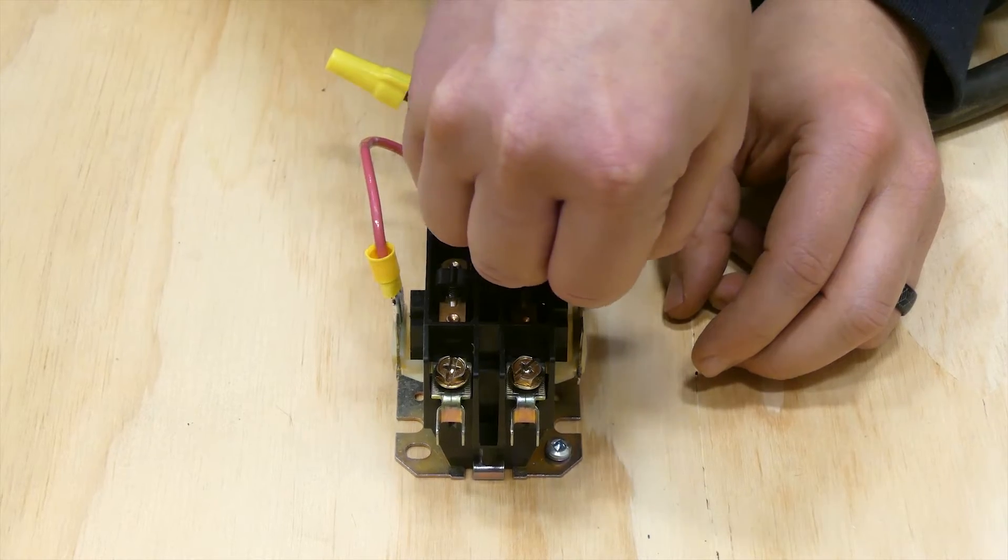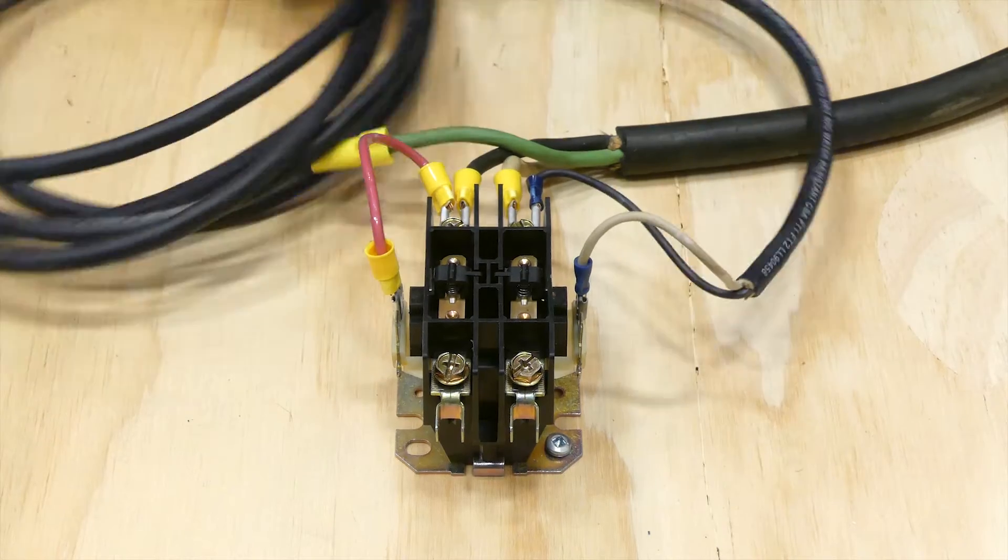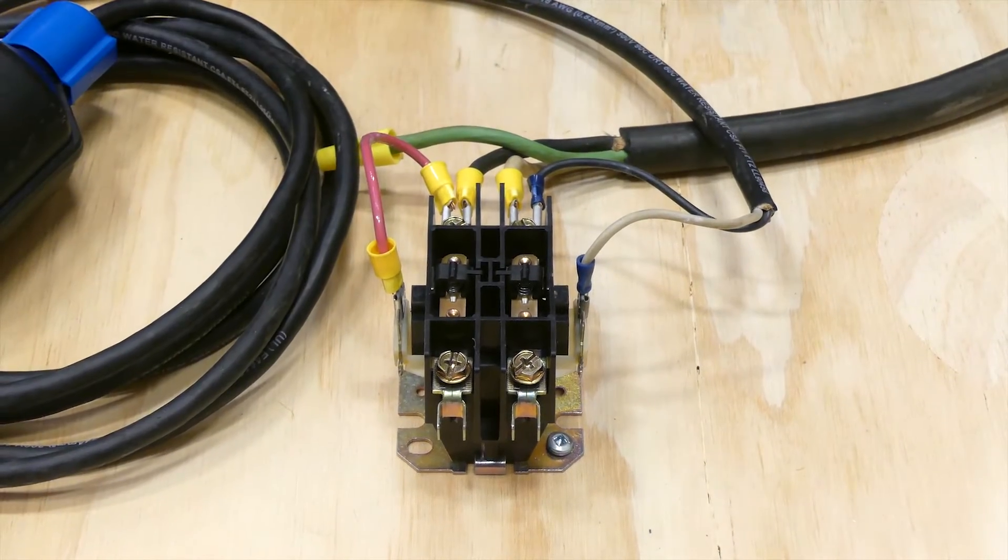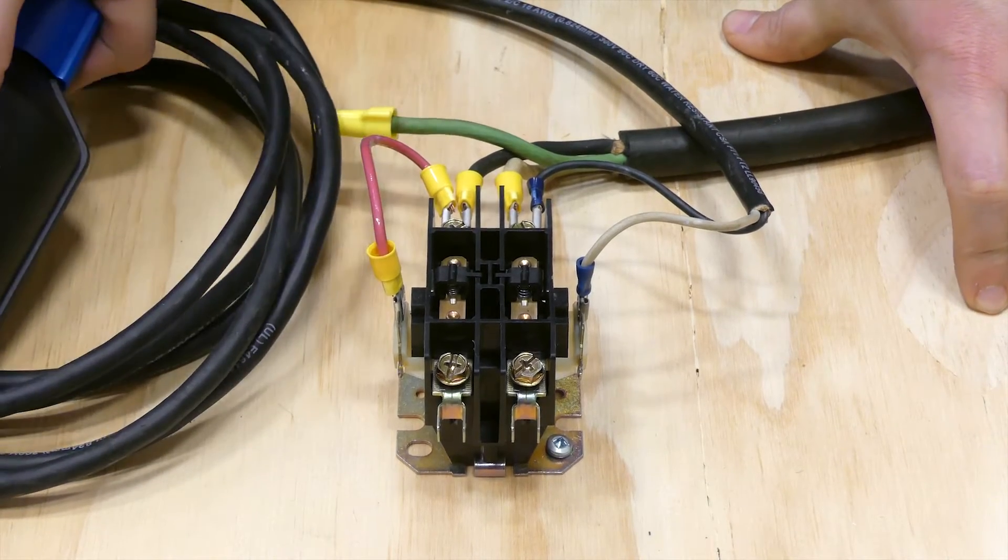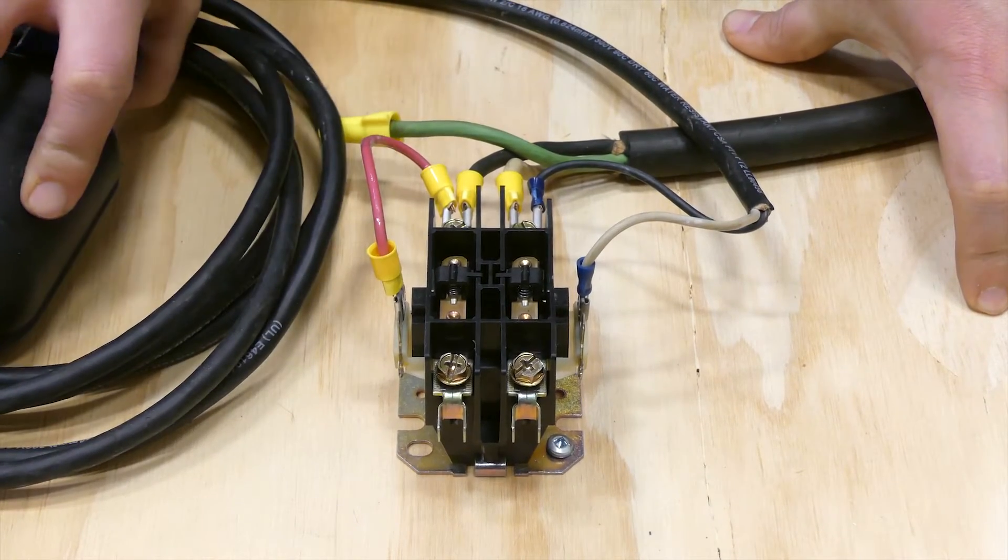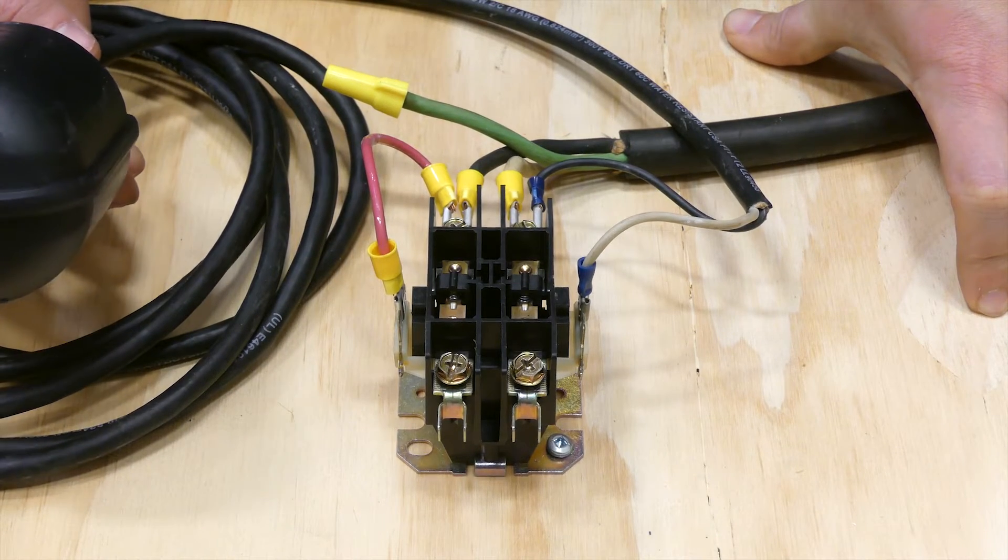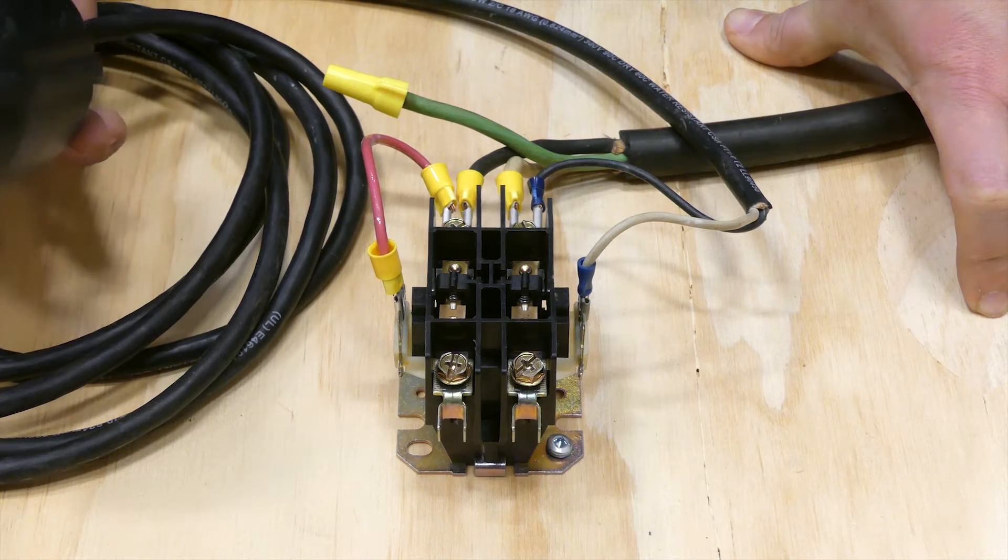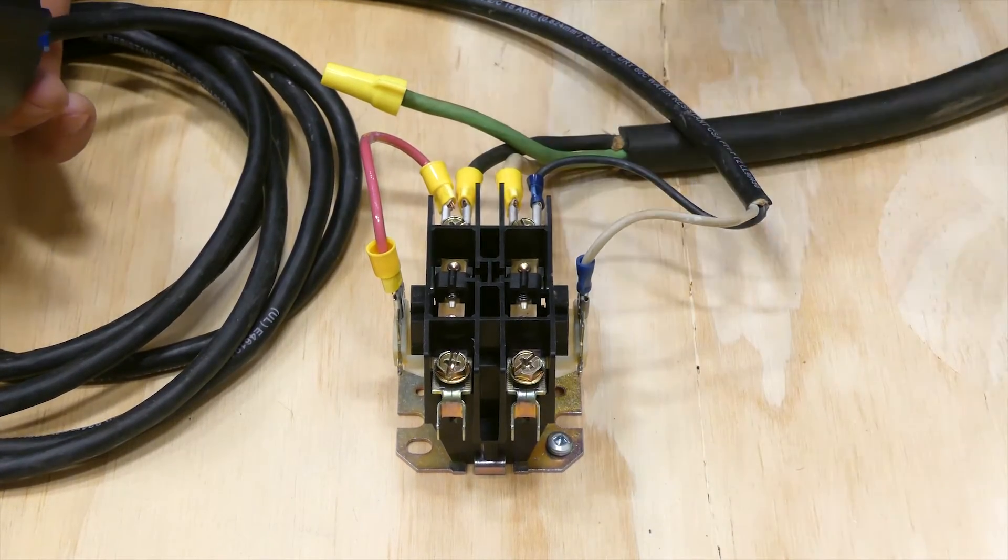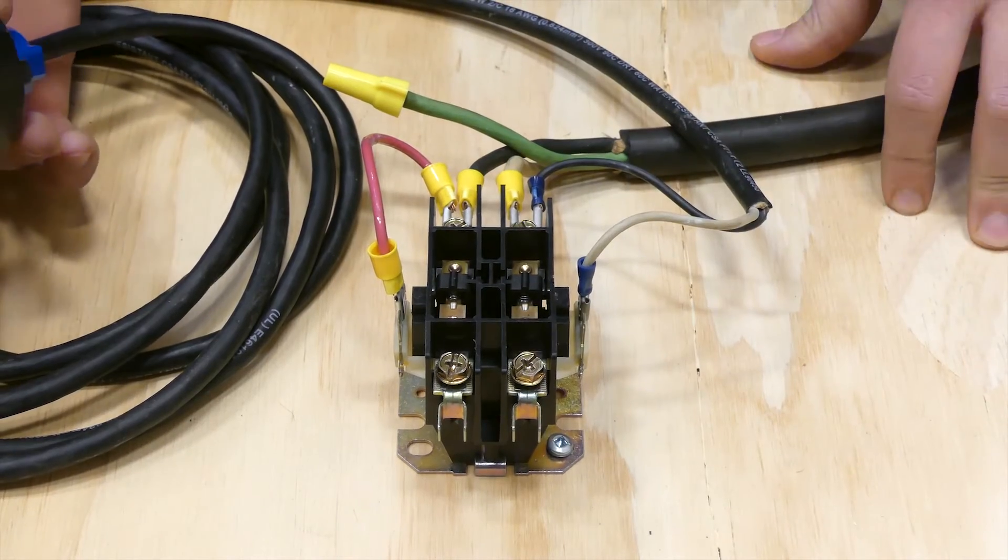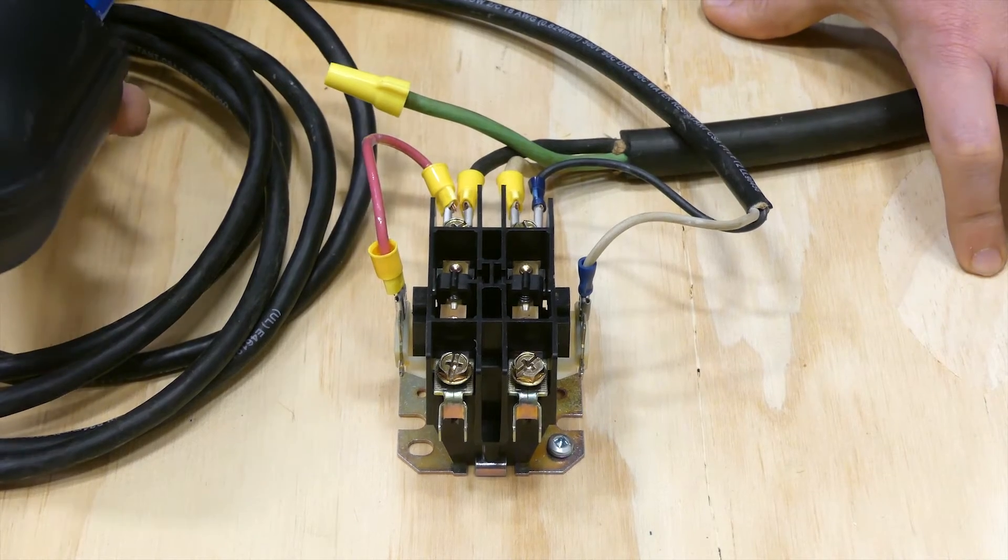So now with our float switch I will turn the power on. So now in this configuration this is a normally open or pump down float switch. And so when we raise this switch up, the water level in the tank is high and so the switch was raised up and the contactor is pulled in sending voltage through the bottom of the contactor.